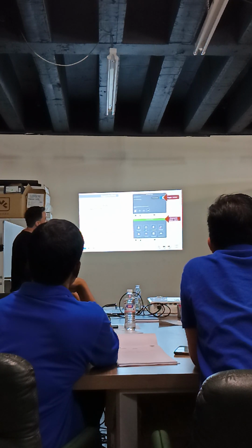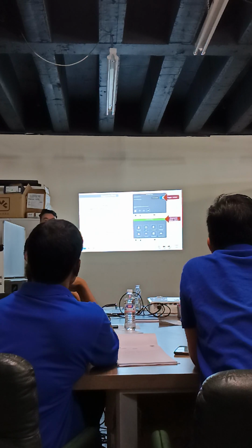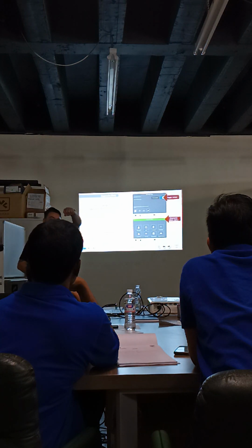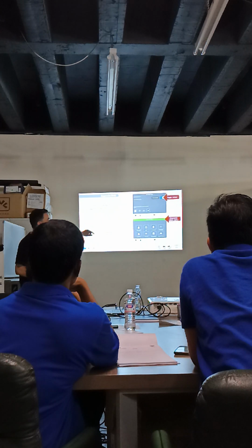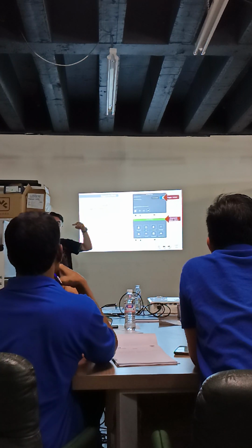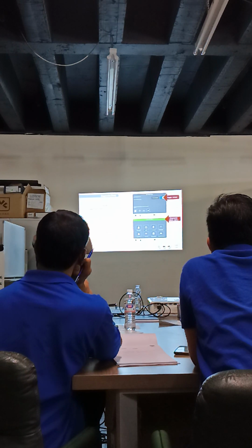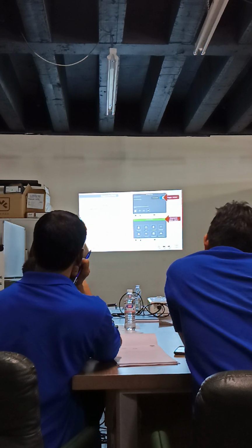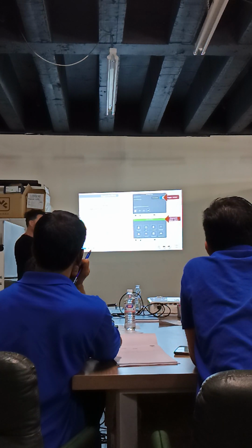So now what I do is go to switch states, press this button, and it's going to say latch, raise, standby. Latch is the switch at the back - remember the electronic switch, magnetic switch? That's the latch switch. Raise is the red button, standby is your black button. So I go to the back of the grill and either bring the platen down to activate the switch, and on the screen it's going to say latch off - when it activates the switch, it says on. Off, on, off, on. I go to my raise button - off on the screen, press it, on. Off, on, off, on. Same with the black - off, on, off, on. I've now just tested all my buttons and the whole system for the upper platen.